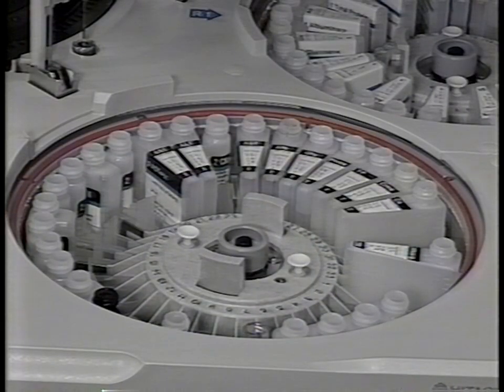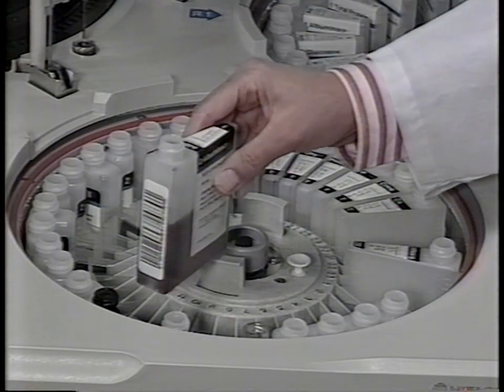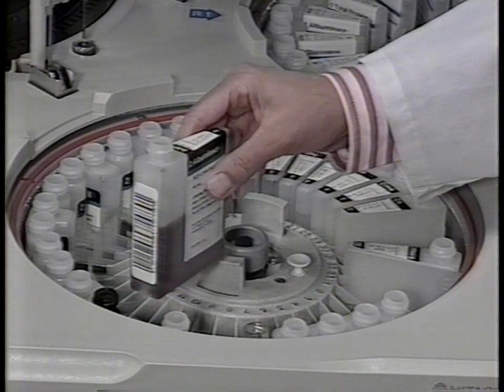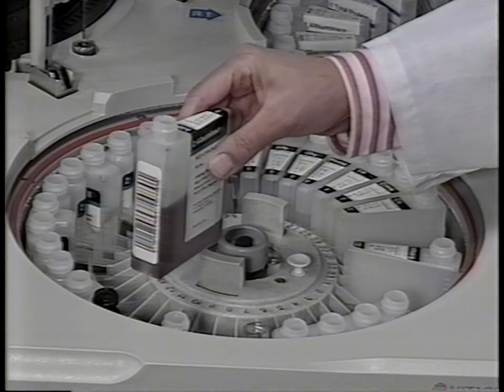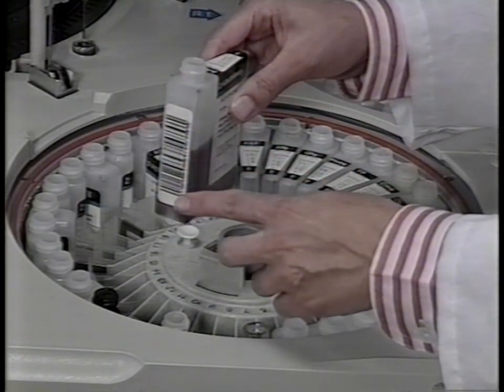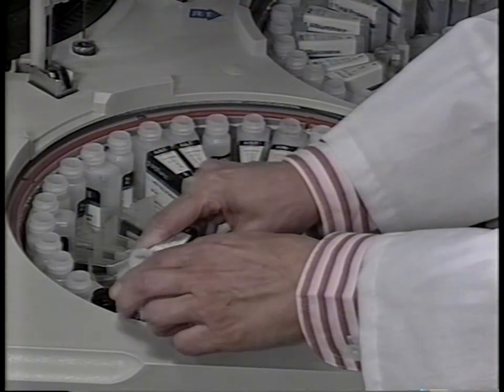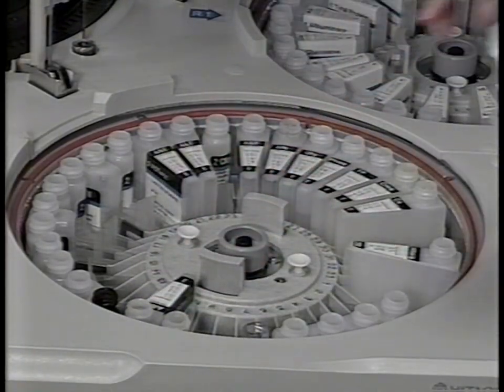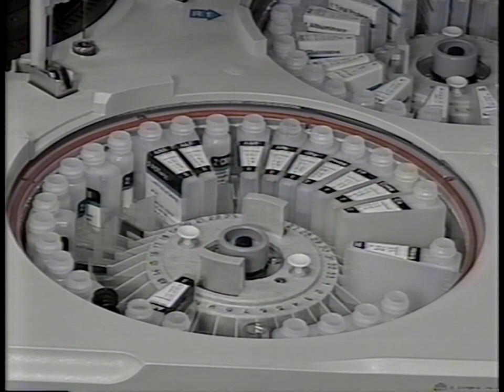When the test associated with a new bottle of reagent has to be calibrated, the analyzer does it automatically using the barcode information. The calibration is automatically followed by controls before the analyzer begins using the new bottle for patient samples.